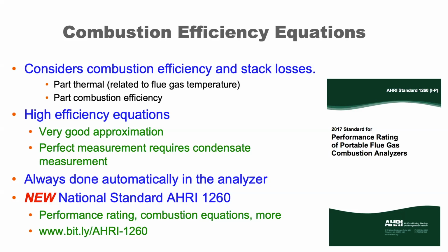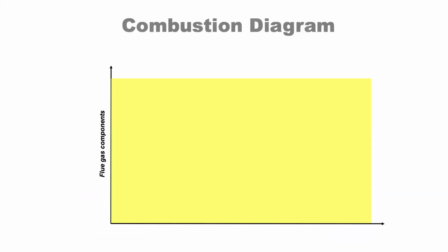It should be listed in their specifications, or if it's one that we carry, we try to list that on our website. So you can pick up the standard for free at this short link here, bit.ly/AHRI-1260. It'll take you to a PDF of the standard. Some interesting reading if you're into the geeky parts of combustion analysis. It'll tell you how the manufacturers are trying to design equipment that can provide consistent readings, and that's what we all want to have.